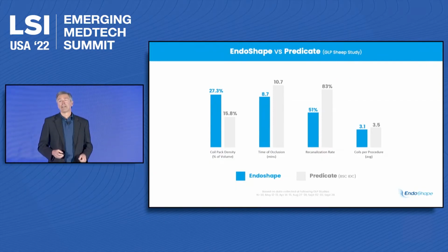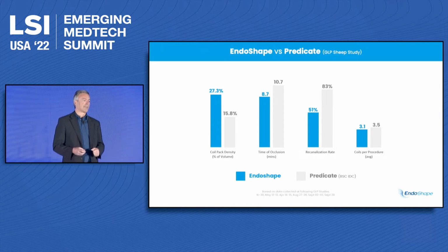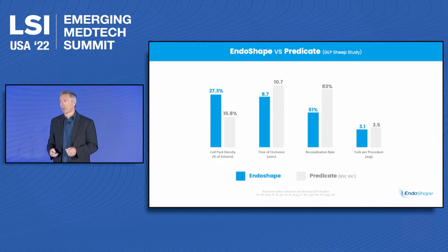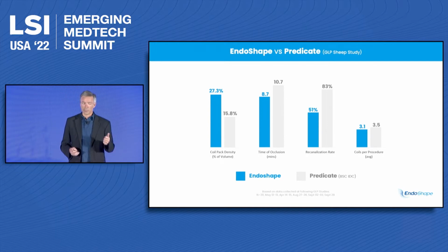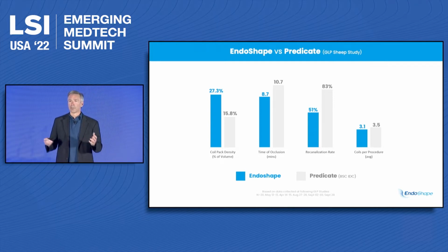In a head-to-head comparison in a GLP animal study, we compared ourselves to the Boston Scientific IDC coil, which we consider to be the best coil on the market. We found that we had a much higher coil pack density, which is good. That created a faster time of occlusion, which again is good. We had a much lower recanalization rate over time, again, better. And nearly half a coil less was used in the study per site in order to create this. So we feel we have a much better product.